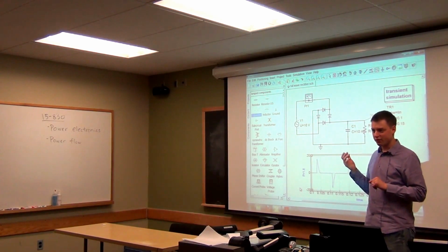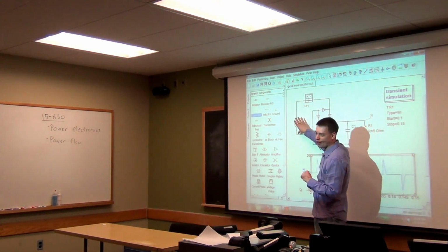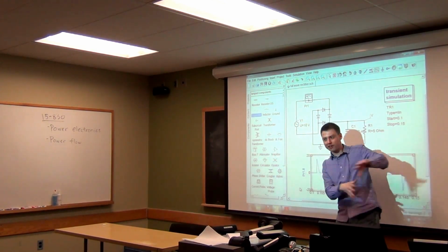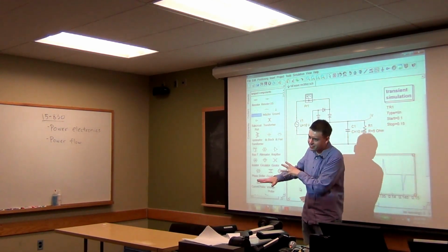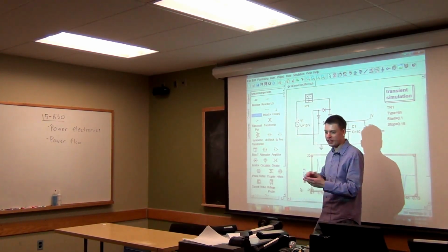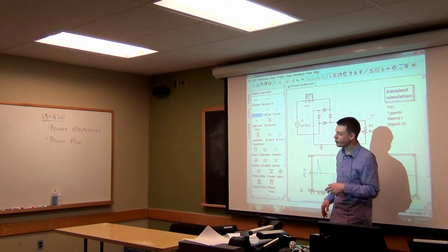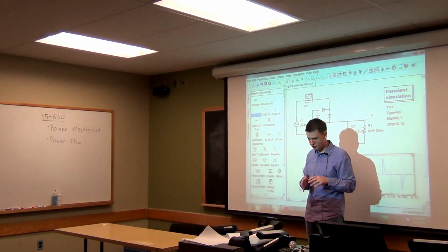So from a utility standpoint, they don't like the fact that you're, say, drawing no current at all, and all of a sudden we draw a ton of current from them in their waveform, then stop entirely. Because the peak here, for example, will be a lot bigger than the peak you would draw otherwise. I mean, to provide the same amount of power, you're drawing a whole lot more current there. When you have these I squared R losses, this is kind of bad.